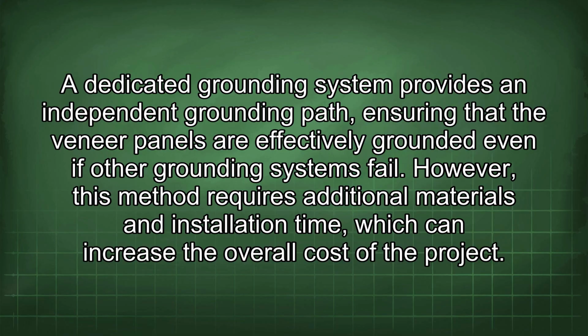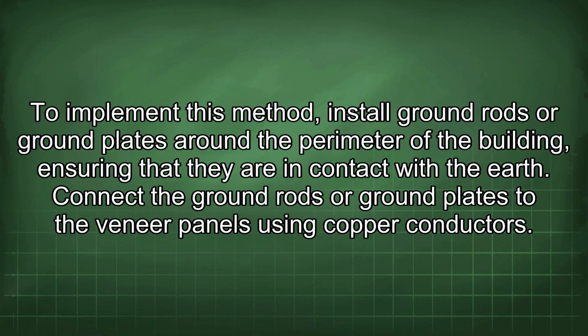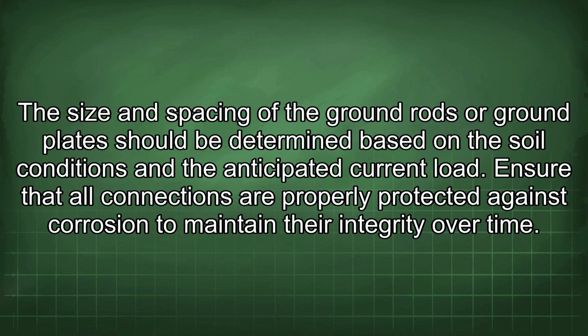However, this method requires additional materials and installation time, which can increase the overall cost of the project. To implement this method, install ground rods or ground plates around the perimeter of the building, ensuring that they are in contact with the earth. Connect the ground rods or ground plates to the veneer panels using copper conductors. The size and spacing of the ground rods or ground plates should be determined based on the soil conditions and the anticipated current load. Ensure that all connections are properly protected against corrosion to maintain their integrity over time.